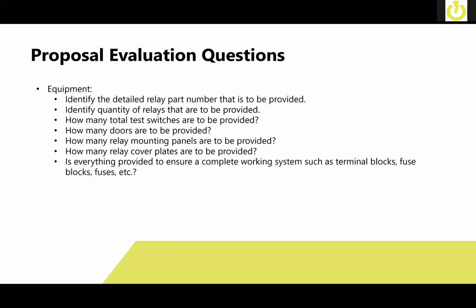From an equipment standpoint, identify the detailed relay part numbers to be provided. A lot of manufacturers nowadays have multiple options in the relays, and the price can range anywhere from $950 up to several $1,000s per relay, depending on the specific application that's needed. So if you're trying to compare apples to apples on a quote and somebody quotes you the bare bones and it's really not what you want, you could get hit with either equipment that you don't want installed or a rather large change order at a later time.